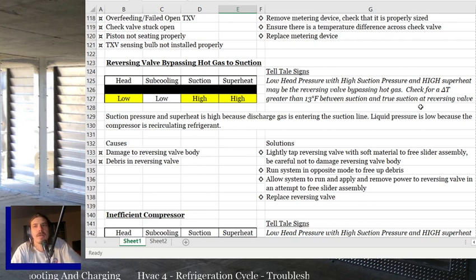So it's not really that the superheat is high, it's just that there's hot gas going in the suction line. So that's why the superheat is high, and it'll usually be really high. Like, you're sitting there trying to figure out how it's 70 degrees inside, but the suction line is 80 degrees high. It'll be really, really high superheat most of the time.